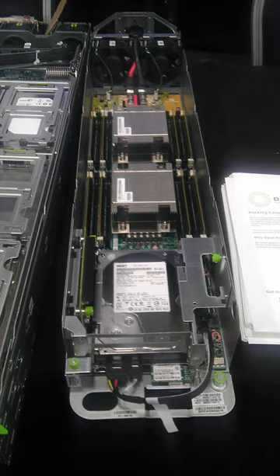Mechanical mounting system: Open Racks have the same outside width and depth as standard 19-inch racks, but are designed to mount wider chassis with a 537mm width. This allows more equipment to fit in the same volume and improves air flow.